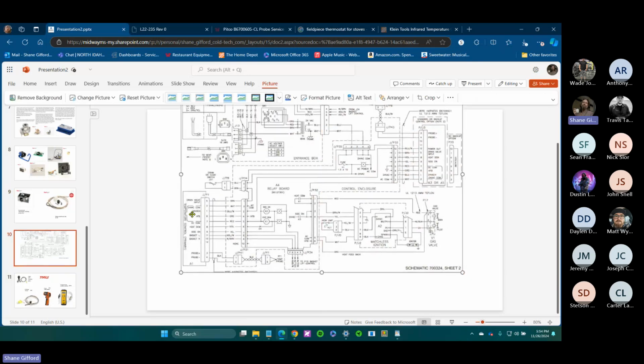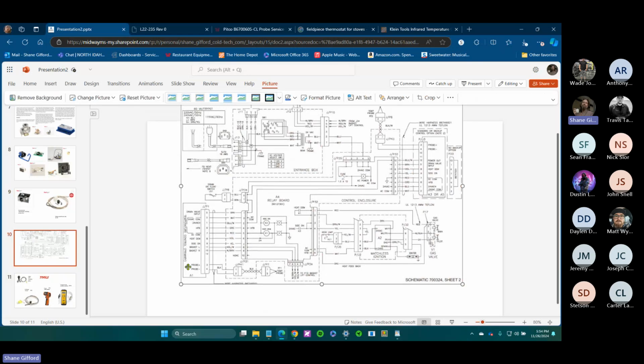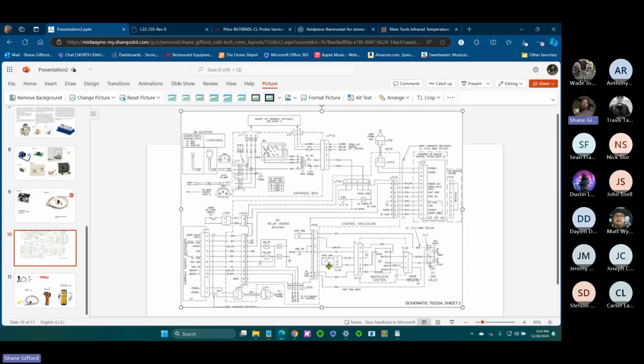Low voltage, here's your temperature control, drain valve input, 24 volts common. You're going to see a big plug, and then these wires are just going to scatter all over the place. But eventually, those wires do make themselves to each of the loads. Got a high limit in there, showing that on this right here, between 1 and 2, you're going to have a high limit.